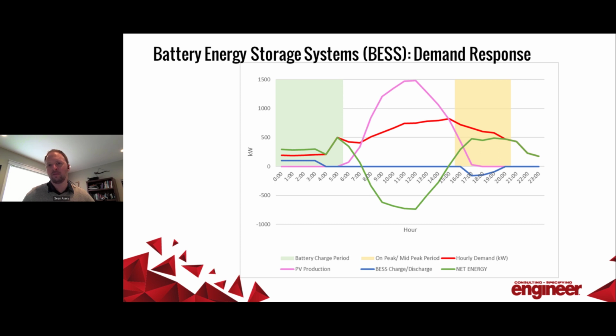So that's where the batteries come into play. The blue line is the battery function, where we're charging at the left of the screen in the green area in the middle of the night. Then when we hit that on-peak window, the batteries start discharging to help reduce that demand even more, and the net result is the green curve.